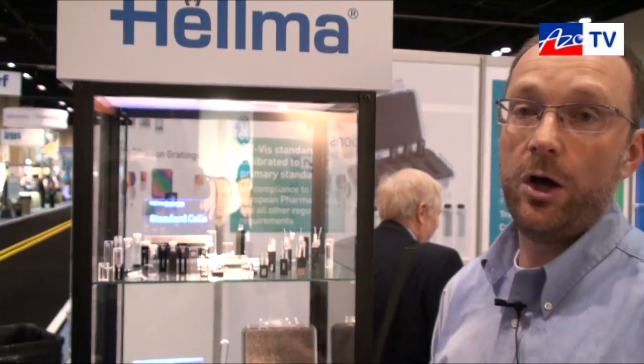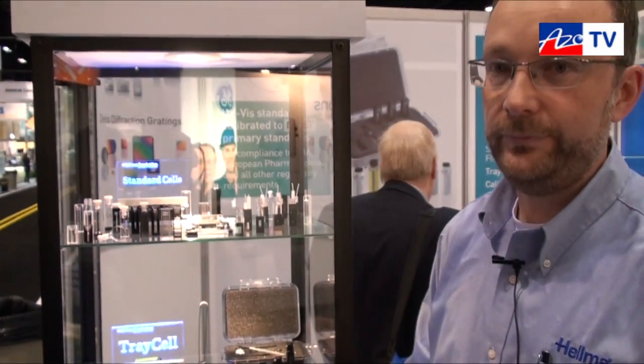This process is not widely known in the world and is what delivers our very high precision products — whether a simple quartz glass cuvette, a cytometer cell, or any other product. It's not just the ability to polish quartz; the ability to bond them, keep tolerances, and avoid warping from high temperature exposure is another unique skill. Ideally, these parts shouldn't be visible at all in your optical measurement. Because light traveling through these windows is almost unaffected, the flatness, parallelism, and wavefront distortion of the windows are very, very low — and we can maintain this quality consistently at a high level through our manufacturing capabilities.